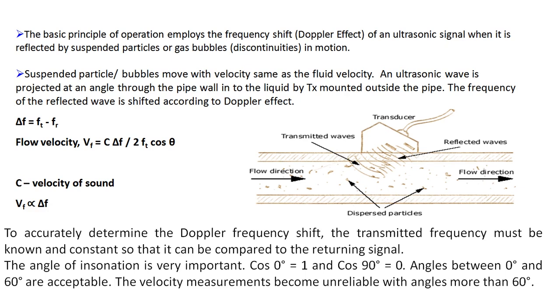The velocity of the moving fluid is directly proportional to delta f. To accurately determine the Doppler frequency shift, the transmitted frequency must be known and constant so it can be compared to the returning signal. The angle at which the transducer injects waves into the pipe is very important — cos 0° equals 1 and cos 90° equals 0. Angles between 0° and 60° are most commonly used.